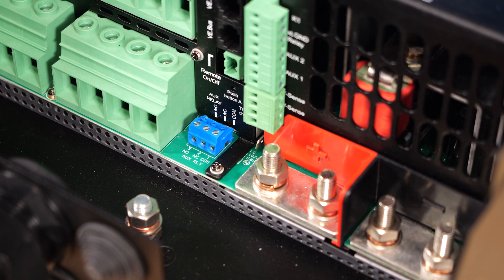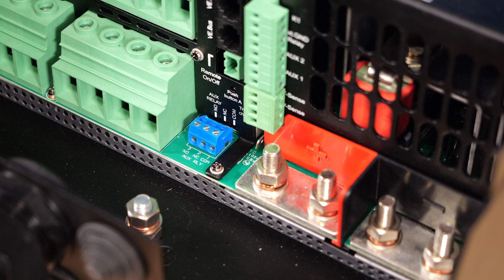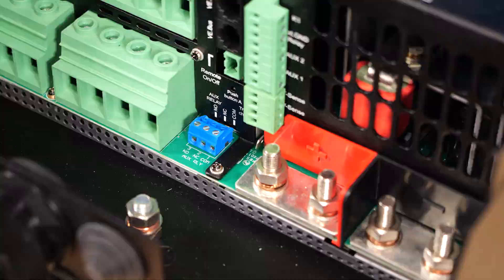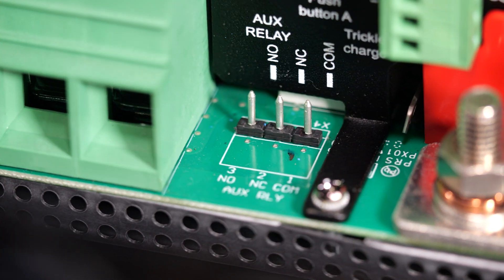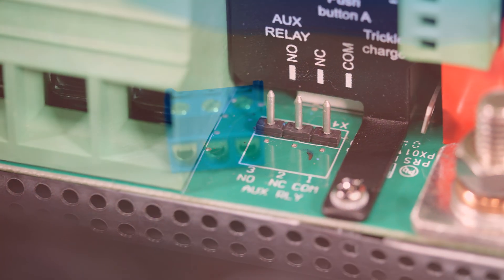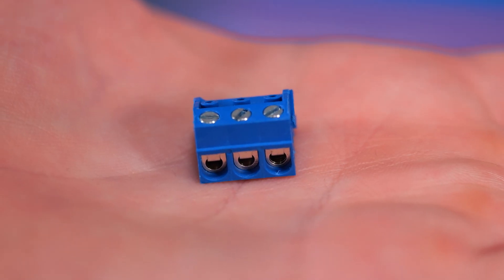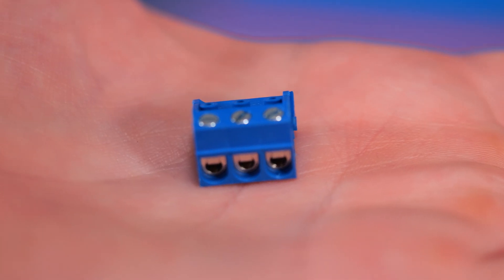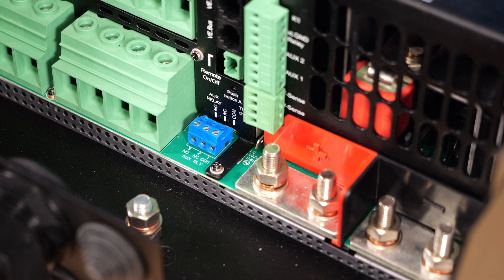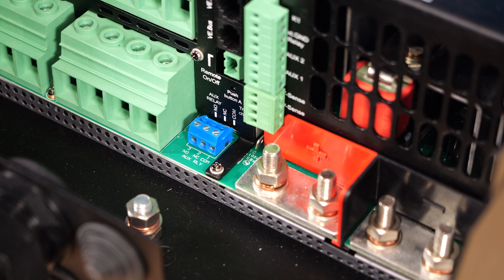At the very bottom of the wiring compartment, we have this blue terminal block that is labelled auxiliary relay. This is a switch that has normally open, normally closed contacts. The terminal assembly can easily be pulled away from the circuit board so you can do your wiring and then plug it back on once the wiring is complete. The auxiliary relays on these inverters have a long list of programmable functions such as alarm output, auto gen start and external fan control.